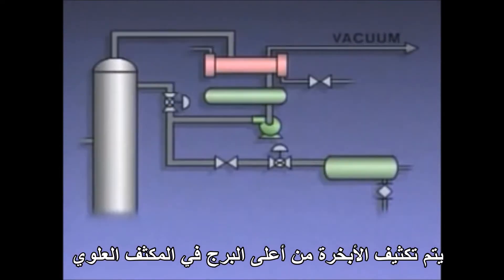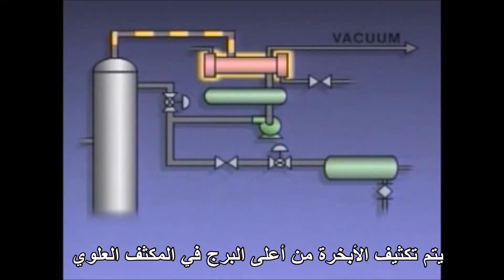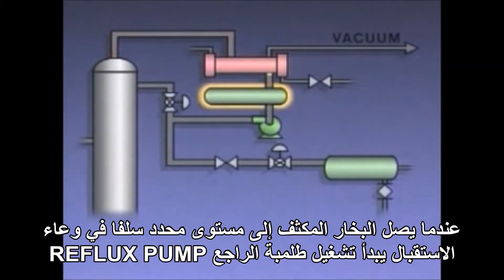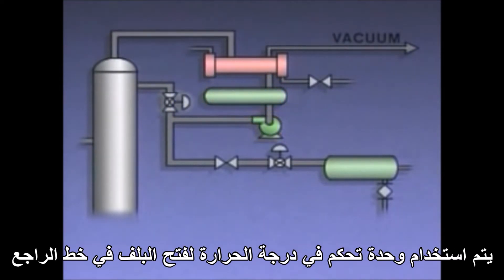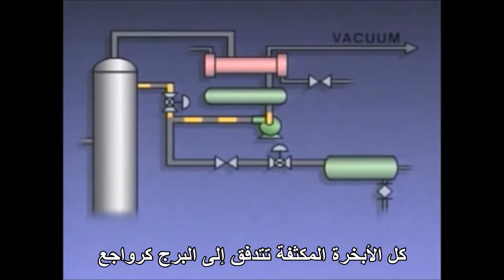The vapor from the top of the column is condensed in the overhead condenser. When the condensed vapor reaches a predetermined level in the receiver, the reflux pump is started and a temperature controller is used to open a valve in the reflux line.